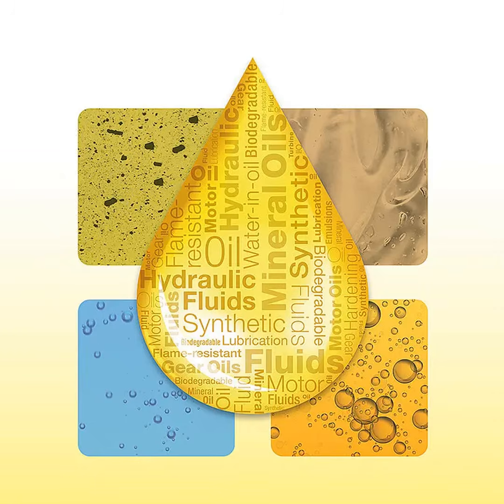Another interesting point is particle size. The human eye can typically only see particles around 50 microns and larger under ideal conditions. Yet many hydraulic filters are designed to capture particles much smaller than that. So a sample of oil might look perfectly clean to us, while still containing contamination capable of damaging sensitive components. Looks can definitely be deceiving.